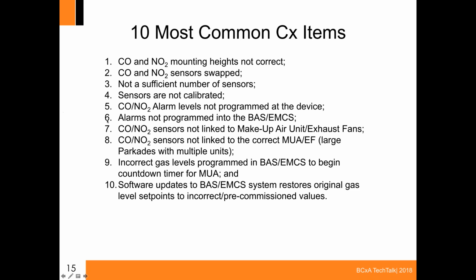The alarm levels were not programmed at the device. It does vary from province to province and state to state, I'm assuming, in terms of what levels you have to alarm at, so getting those correct is important. The most common one is alarms are not programmed into the BAS yet, that the controls contractor has forgotten to do that. The sensors are not linked to the makeup air system, to the ventilation, so even though they are reading high levels, it's not starting up that ventilation equipment. Not connected to the correct makeup air unit system.